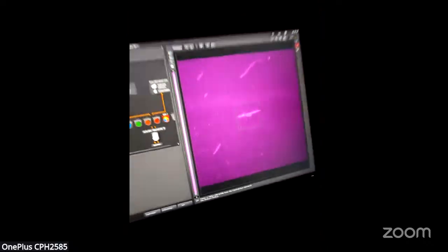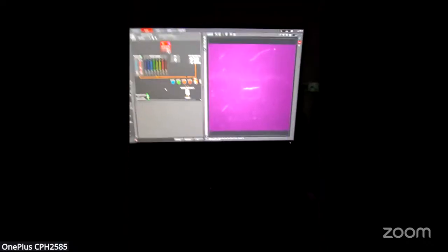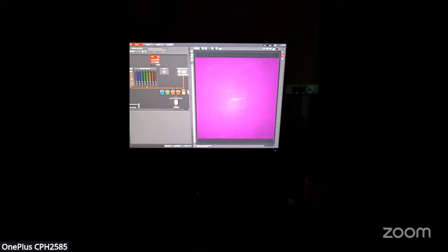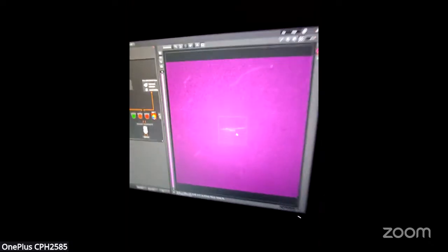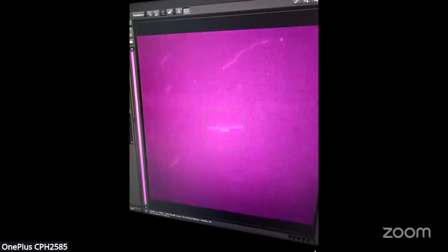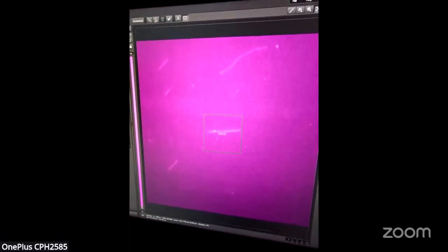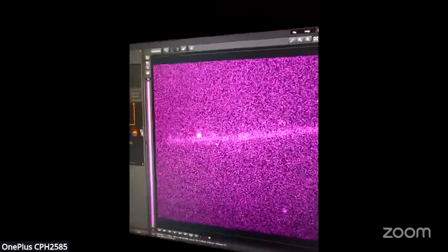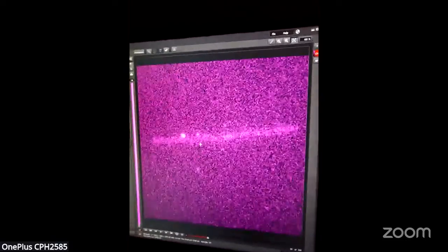And now if you try to focus on the entire screen, you can see while I am capturing the samples, for example, if I go to the epifluorescence, now you can see the signal to noise ratio is less. However, if I go to TIRF, also you will not be able to capture. But if you go to the HILO mode, this is the most appropriate one where you can capture the signal to noise ratio, as you can see here. So the signal to noise ratio will increase in HILO illumination mode as compared to the epifluorescence illumination, the wide field illumination.